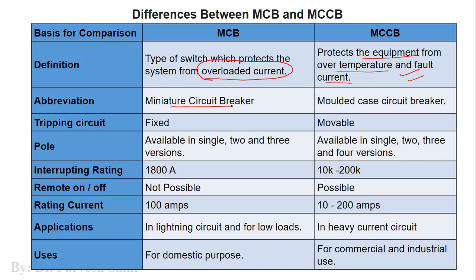MCB stands for miniature circuit breaker, and MCCB stands for molded case circuit breaker. MCB is available in single pole, two pole, and three pole versions, while MCCB is available in single, two, three, and four pole versions. MCB cannot be operated from a remote location — it either operates automatically or manually — but an MCCB can be operated through remote location in addition to automatic and manual operation.